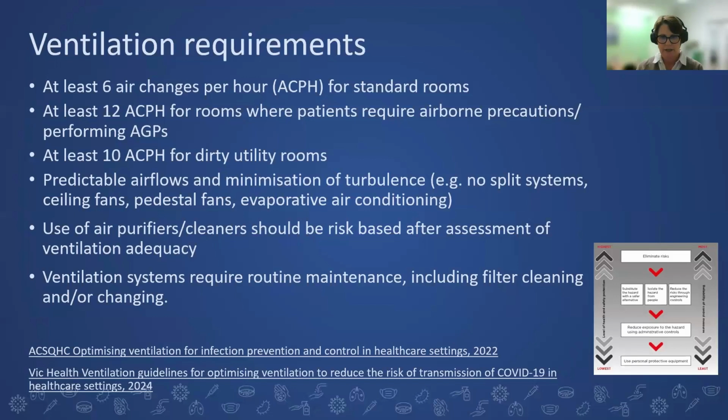Some of the ventilation requirements, and I'm not going to go into all of them, but in particular where you have areas with confirmed positive patients with some of these organisms we've been talking about, the air should be actively ducted to the atmosphere outside of the practice building. We don't want it staying within the building and increasing the risk.